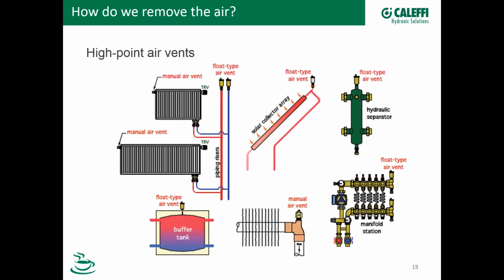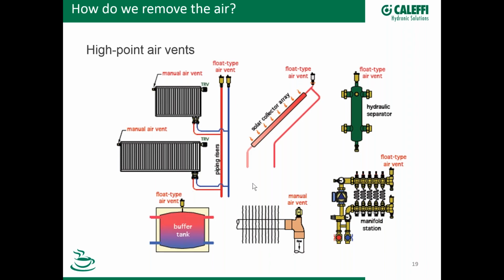Let's talk about devices that are used to remove the air. So high point air vents are one, and you can see a bunch of pictures here that show where air vents are located. For example, at any high point in the piping, as shown here, on the top of a solar collector array, on the top of a hydraulic separator, manifolds, and other locations. So again, here's the high points that we were talking about.